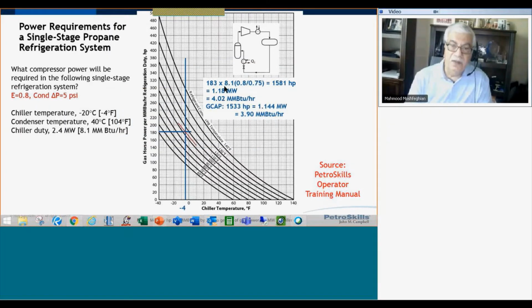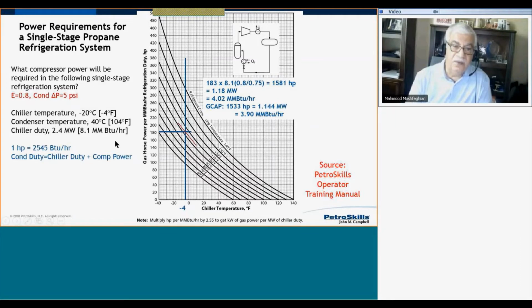duty. So my chiller duty is 8.1 million multiplied by 183. This chart is based on compressor efficiency of 80%, but for my process I use 75%, so I adjust, and the power requirement would be 1,581 horsepower, and compared to the GCAP, not a perfect match, but very close agreement. And if I have the compressor power requirement, I can add chiller duty to it to get the condenser duty as well. So if I do the condenser duty calculation, the chart gives me 12.12 million BTU per hour, and GCAP gave me 12.04 million BTU per hour.